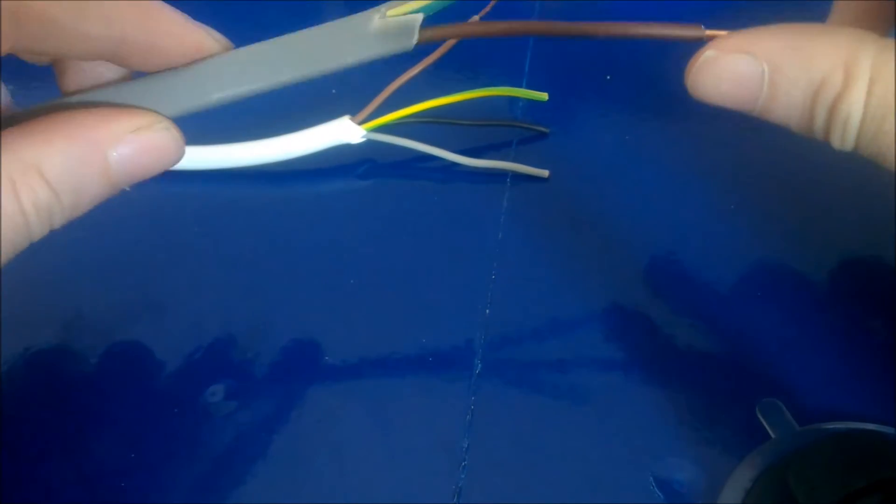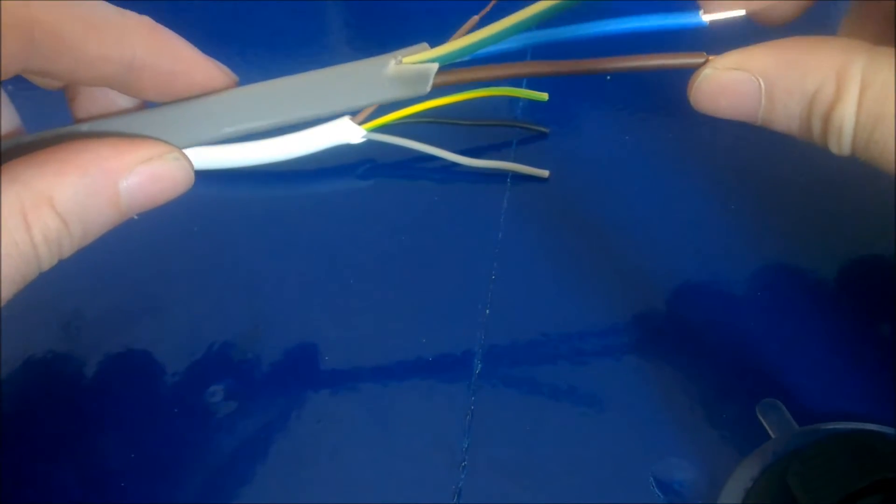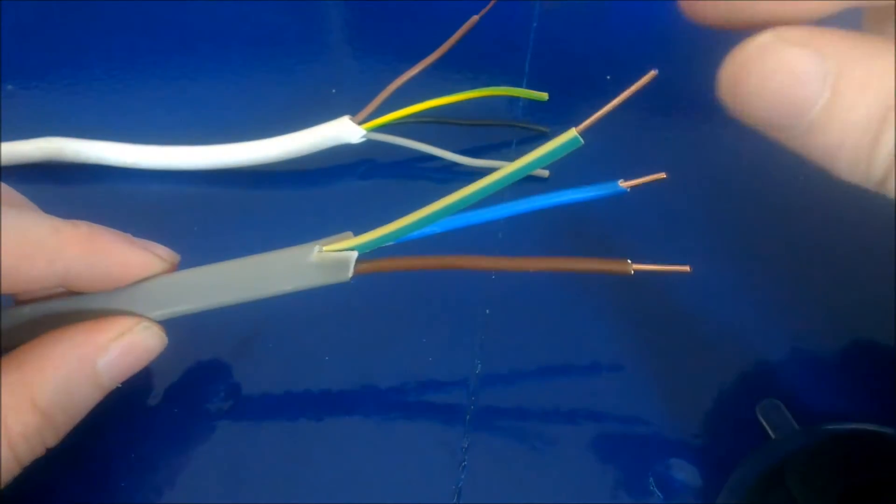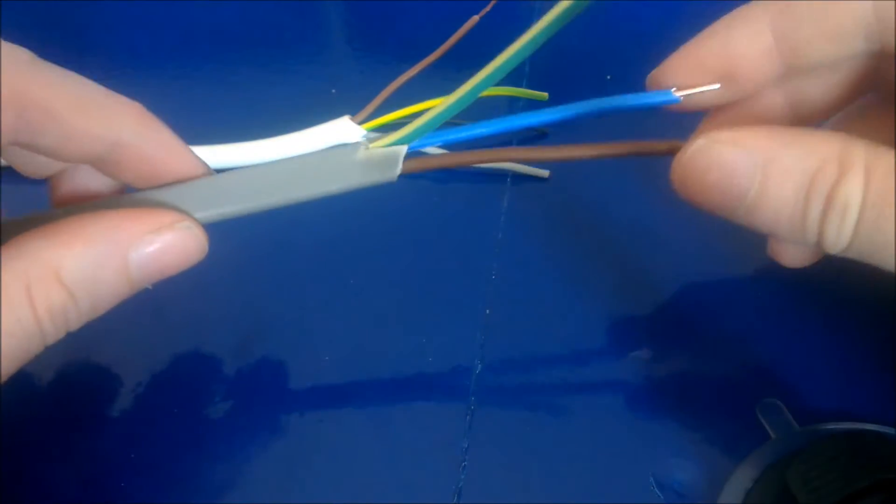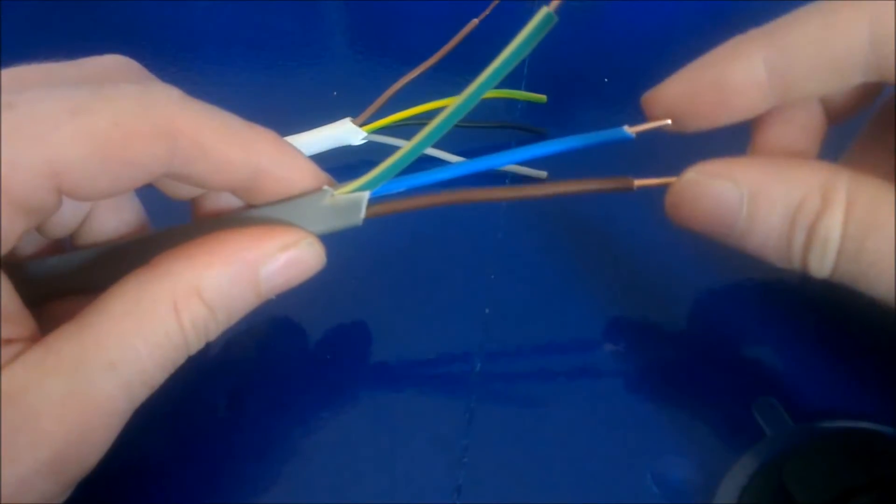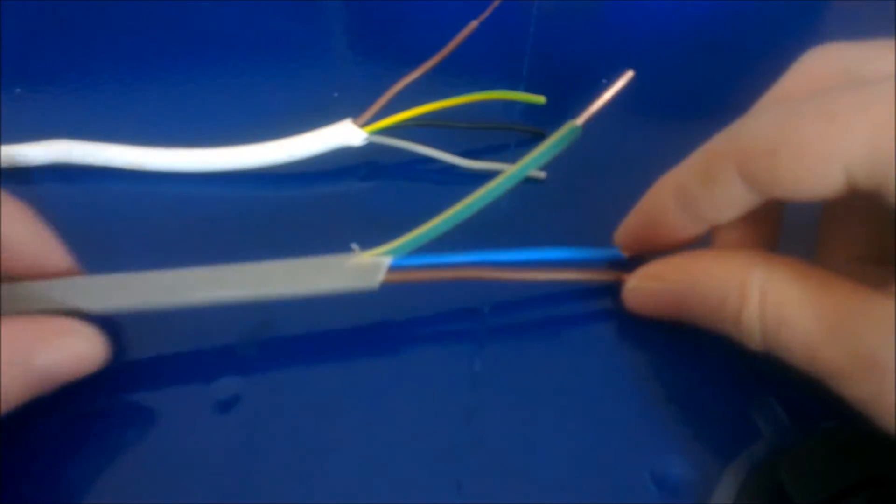So two cables, live and neutral, are 2.5mm, and then your earth is 1.5mm. It doesn't have to be as big as the live and neutral cables. It's installed in a ring circuit, so it leaves the board—live and earth leave the board, round each circuit, and back to the board.